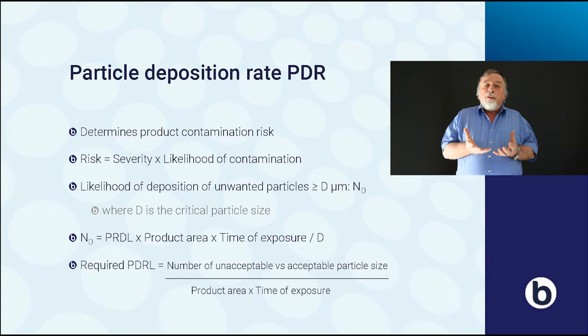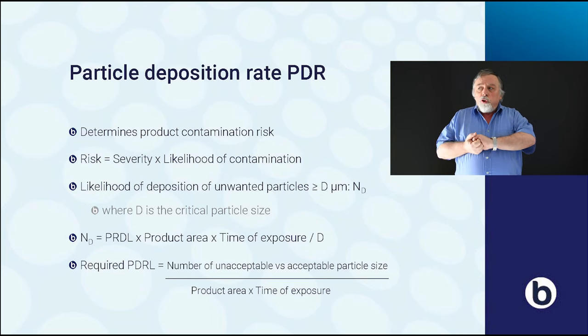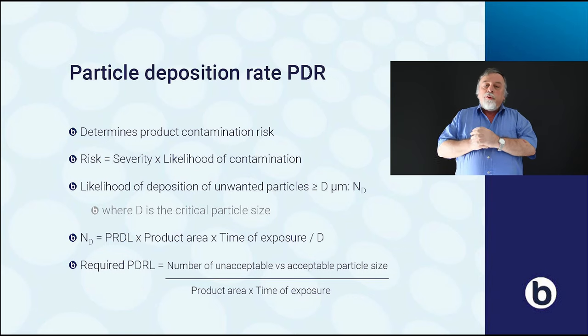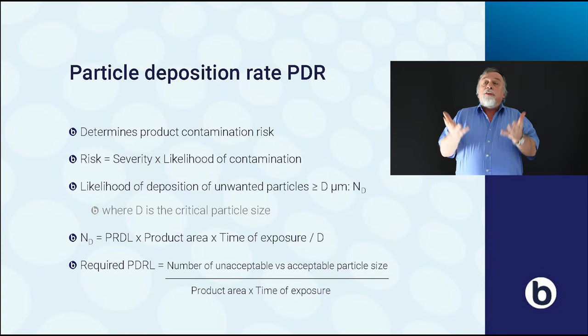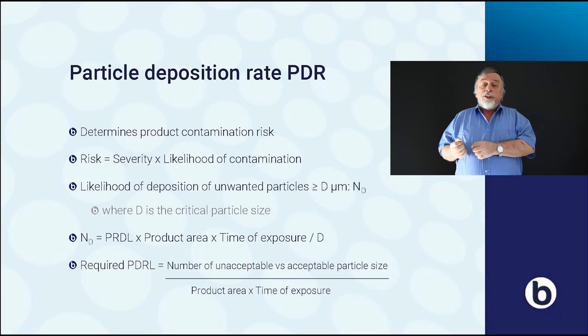Products can be contaminated by particles through deposition, so the particle deposition rate determines the risk of product contamination. Risk is severity times the likelihood of contamination — severity could be high if particles are large and lower when particles are small. The likelihood of particles depositing onto a product is related to the product area and the time the product is exposed. The number of particles larger than d equals the particle deposition rate level times the product area times the time of exposure, divided by the critical particle size d.